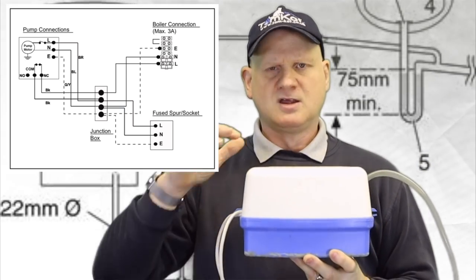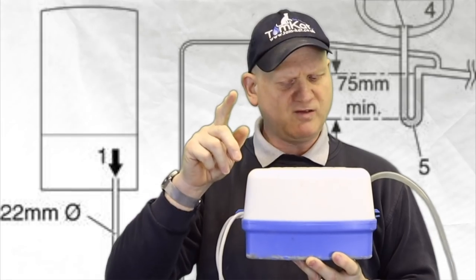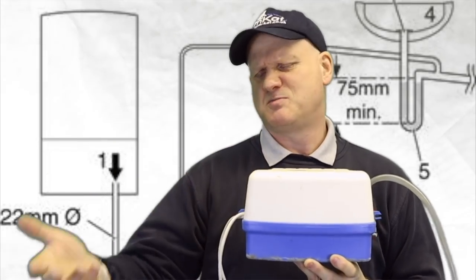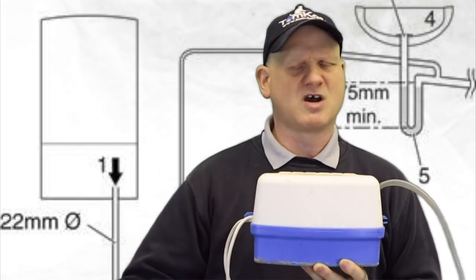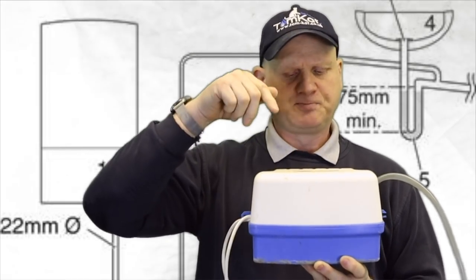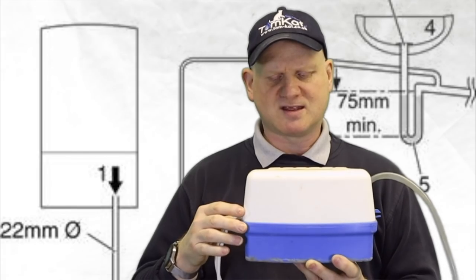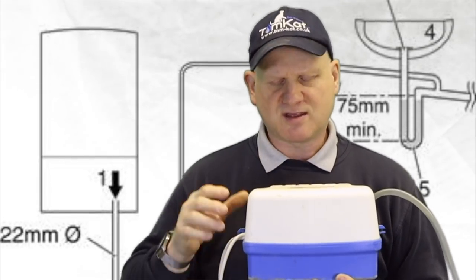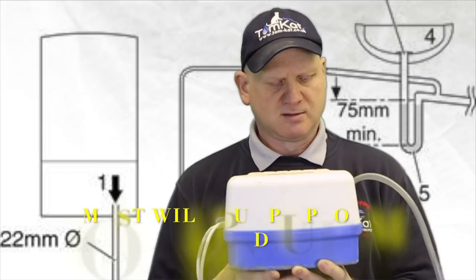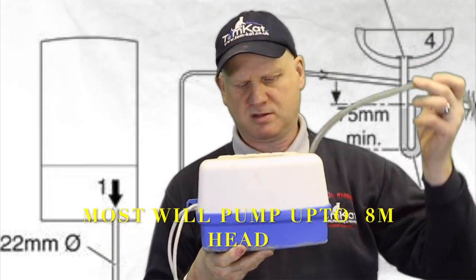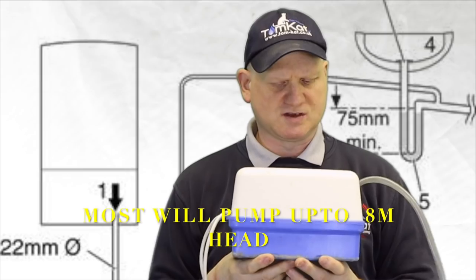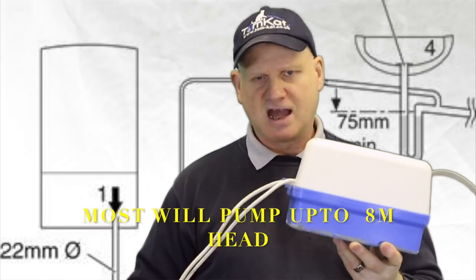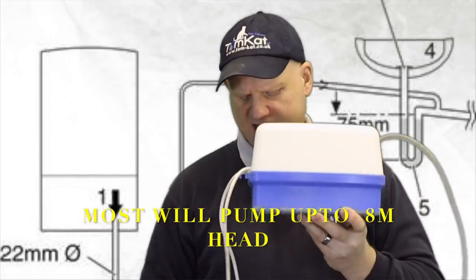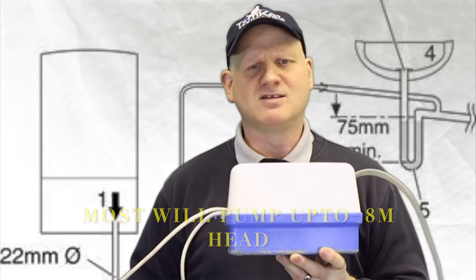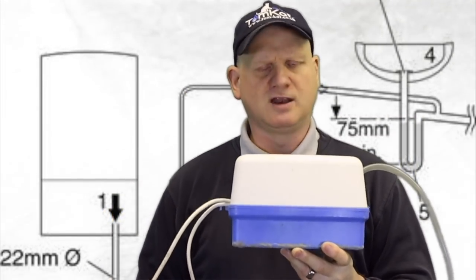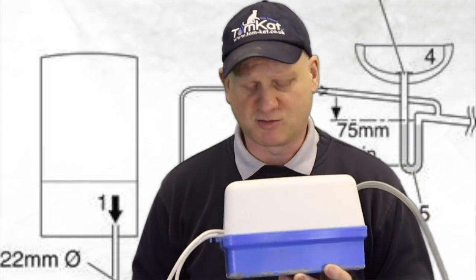So these are also very good if you're in places such as a basement, the boiler's in a basement, or you've got a basement flat, something like that, where the boiler is actually lower than the drain system. So you can actually use this then to pump it higher up, because it does go quite a distance up. Always check your manufacturer's instructions though for your maximum lengths. And always check your boiler manufacturer's instructions how you're going to interlock it into your boiler to stop it working if this stops working.